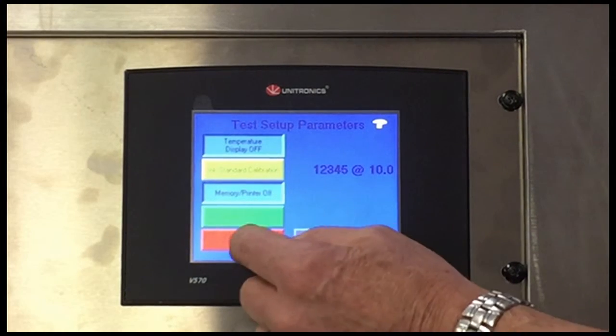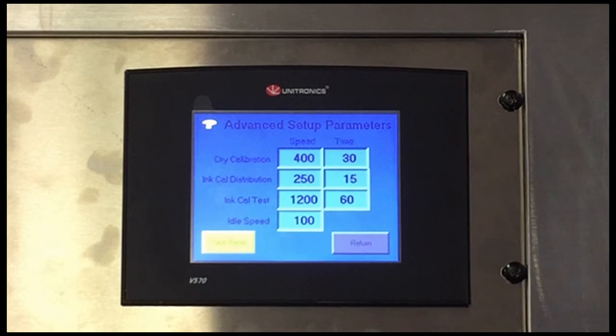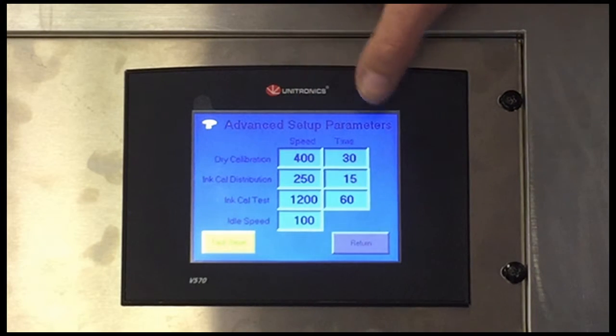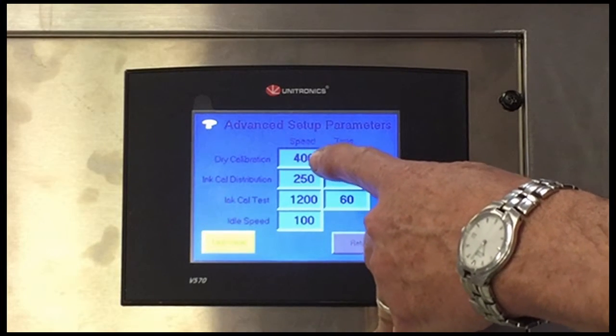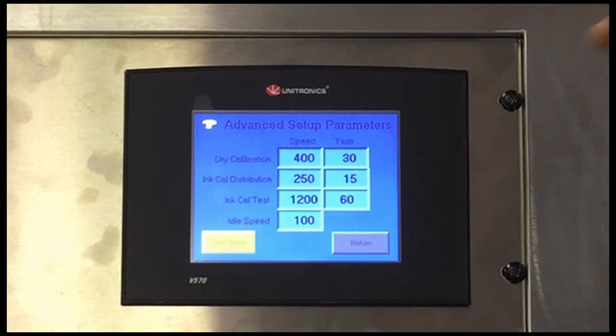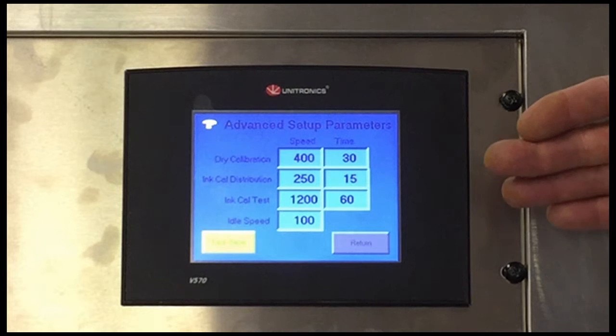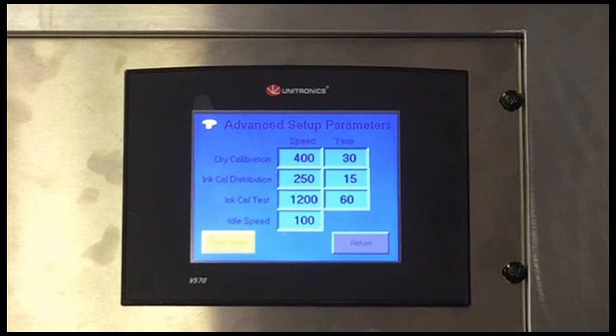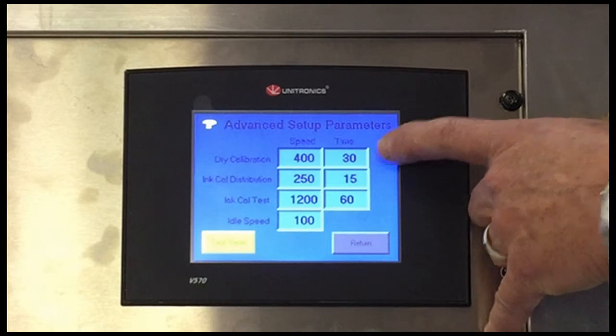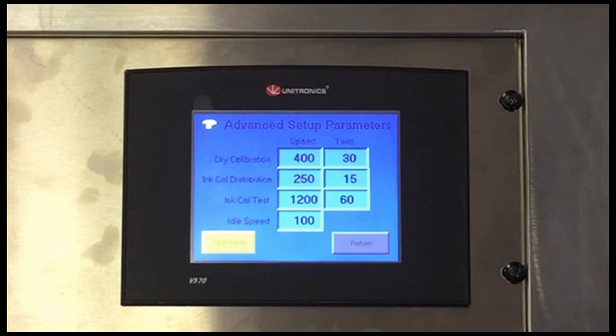Now the other area of interest is we have these advanced settings, and what the advanced settings are is when we actually do our calibration, which we're going to do next, this is where we key in all of the parameters for our calibration. For example, we're going to do our dry calibration only at 400 RPMs, and we're going to wait 30 seconds. What's going to happen in a dry calibration, I don't think we're actually going to do this for this demo because it's very straightforward. But when you start the dry calibration, it's going to tell you to put the calibration rig on the machine and then apply the weights at certain intervals. And what this is telling us is that it's going to wait 30 seconds between each one of these intervals as we apply the weights.